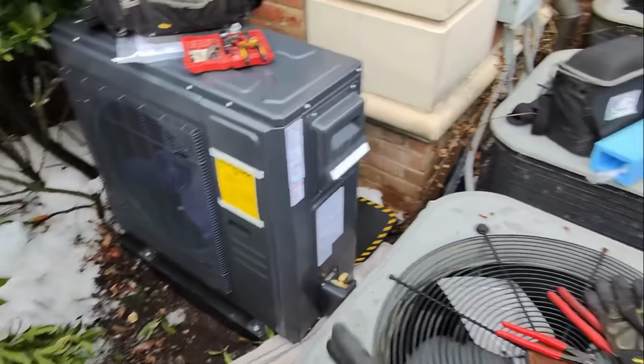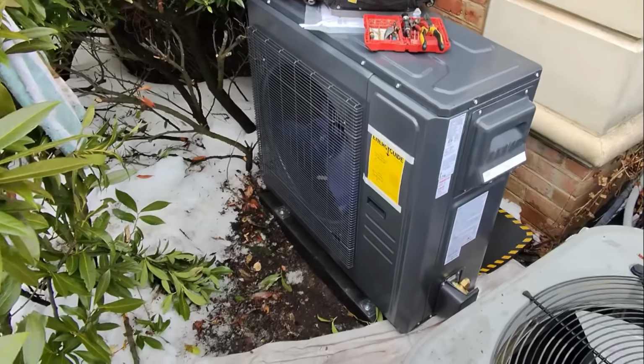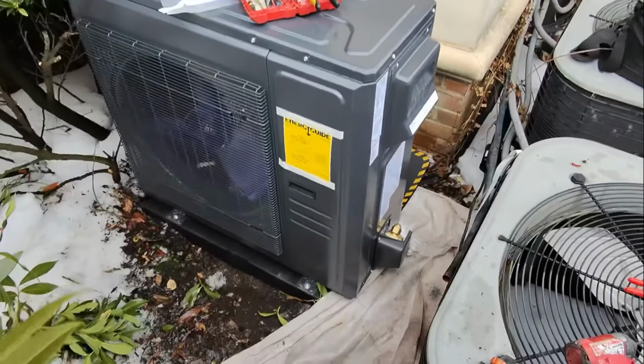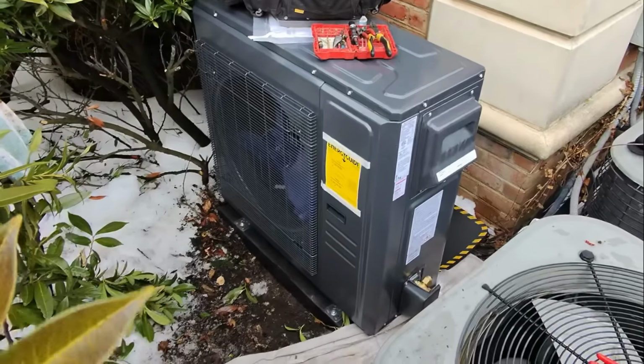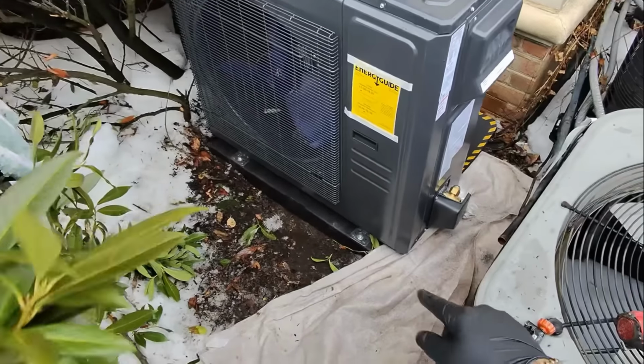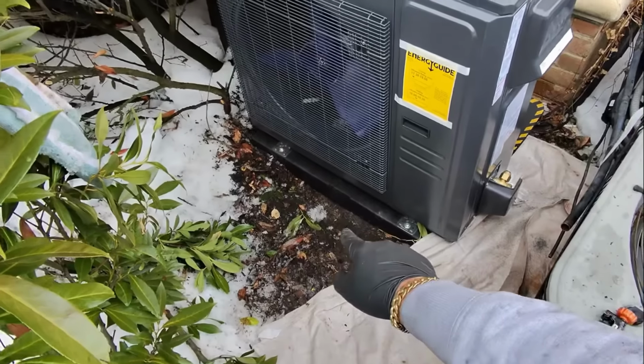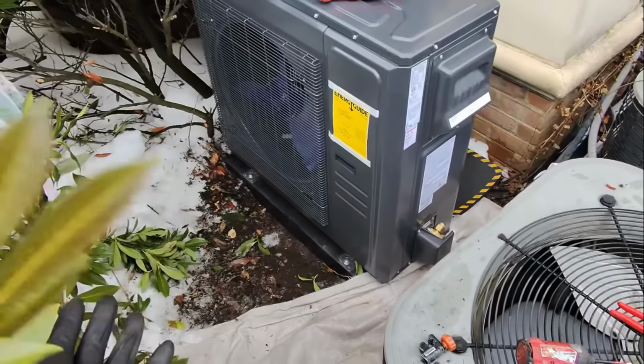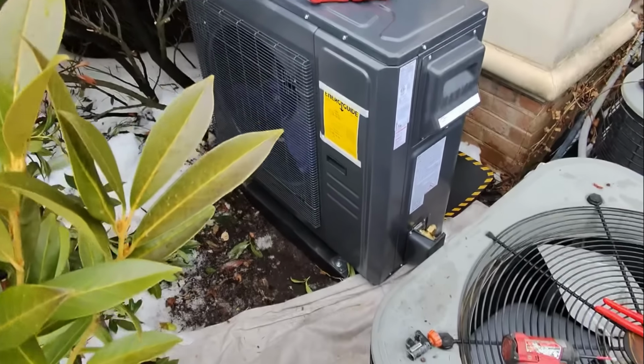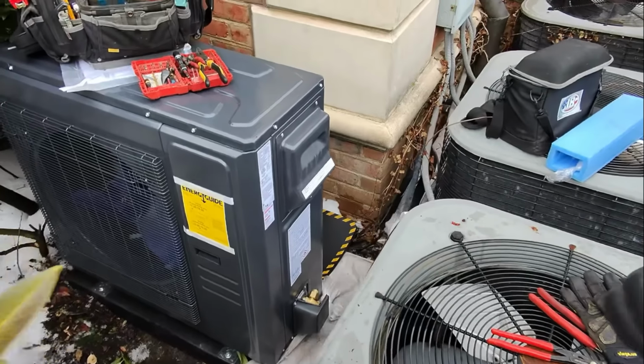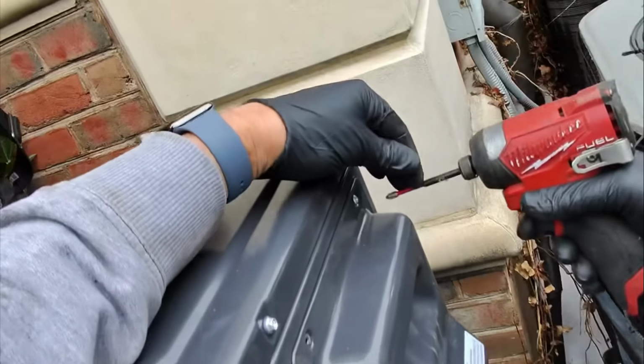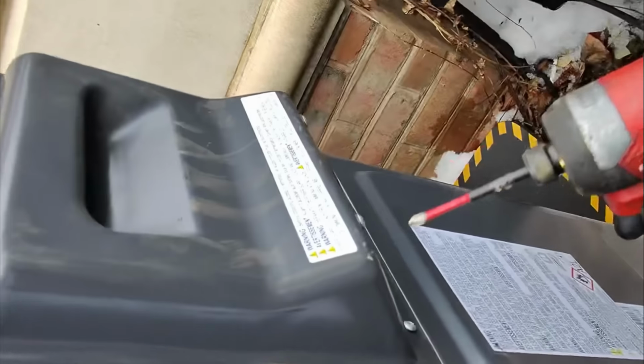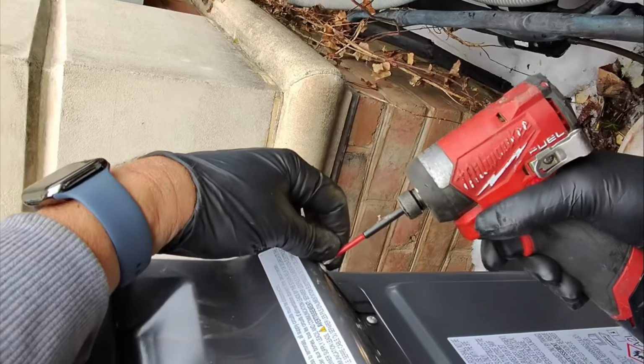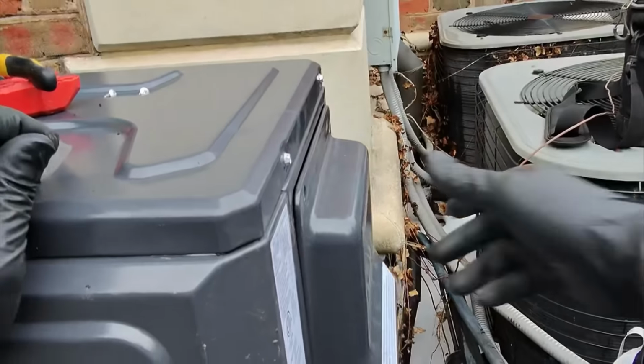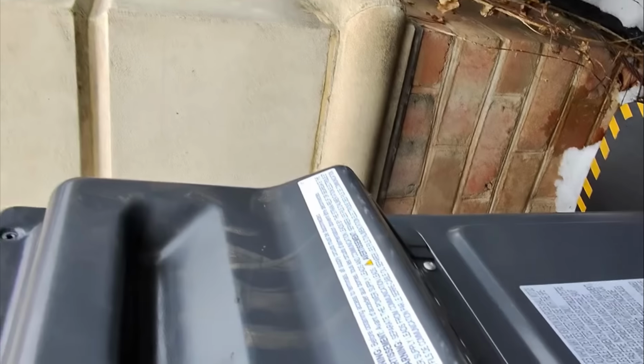I asked the client beforehand, would he like it mounted to the wall? He goes, no, just put it on a standard pad. The outdoor condensing pads that he has in place now were cemented in place when the home was built. So I used 12-inch lag bolts, and I screwed through this new pad for added elevation and into the pad below. We good. It's not going anywhere. That being said, let's work on the electrical, the line voltage and low voltage communication wire. I'm removing the 2 Phillips screws on the top and bottom. That will expose the electrical compartment. Did I miss one? No, it's just glued in. There we go.